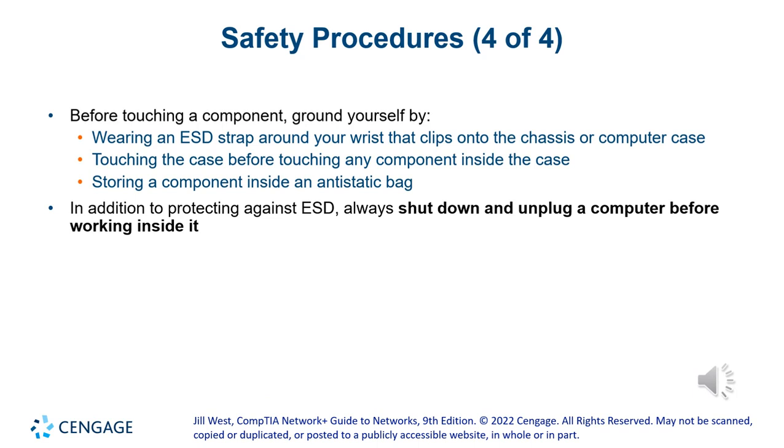Some ways to prevent that include using an ESD strap, right? The ESD strap is a little strap that goes on your wrist, with a metal plate that touches your skin, and you can ground that to any cabinet that has grounding. For network equipment, it's really important to have proper grounding, because the switches do require it. You might see that some enterprise switches have a connection in the back for a grounding wire. Whenever you install those, make sure that the grounding is connected correctly to either the frame or the cabinet where you install the equipment, and that the frame is actually grounded to the proper building grounding. FPL in our town provides grounding on every location.